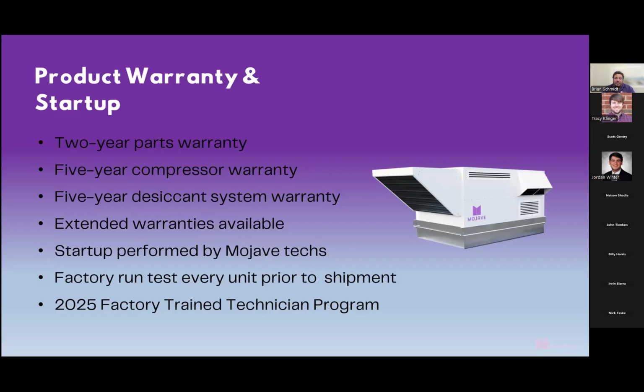So we try to manipulate the environment in the factory, or in a small part of the factory, to replicate the environment that it's going to. And we factory run test these units for about 2 hours each. The reason for that is so we can have that liquid desiccant flowing through the system and know what the volume of desiccant needs to be.